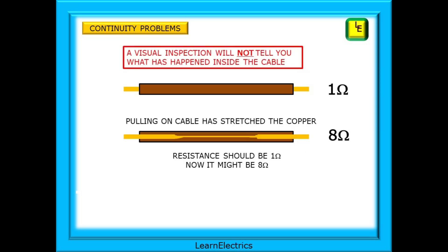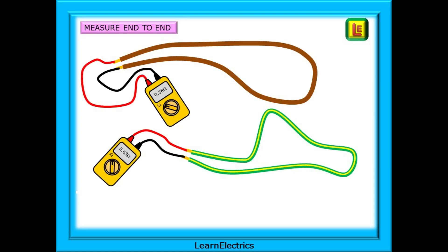Another fault that a visual inspection may not show is when the cable has been stretched, perhaps pulled with some force through conduit or holes in floor joists. Where the cable has jammed, the copper has stretched and become thinner at that point. If it becomes thinner it is no longer the correct size of conductor for the job and will need replacing. Shown here rather dramatically is a cable that has been stretched and now has a resistance of eight ohms, clearly making this cable not fit for intended purpose.